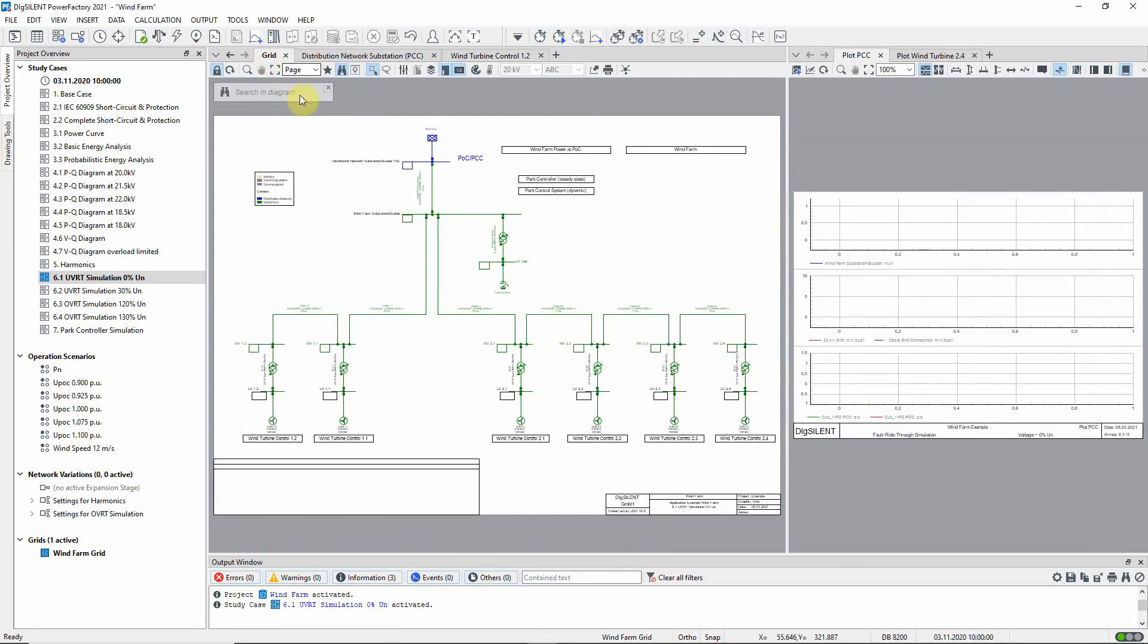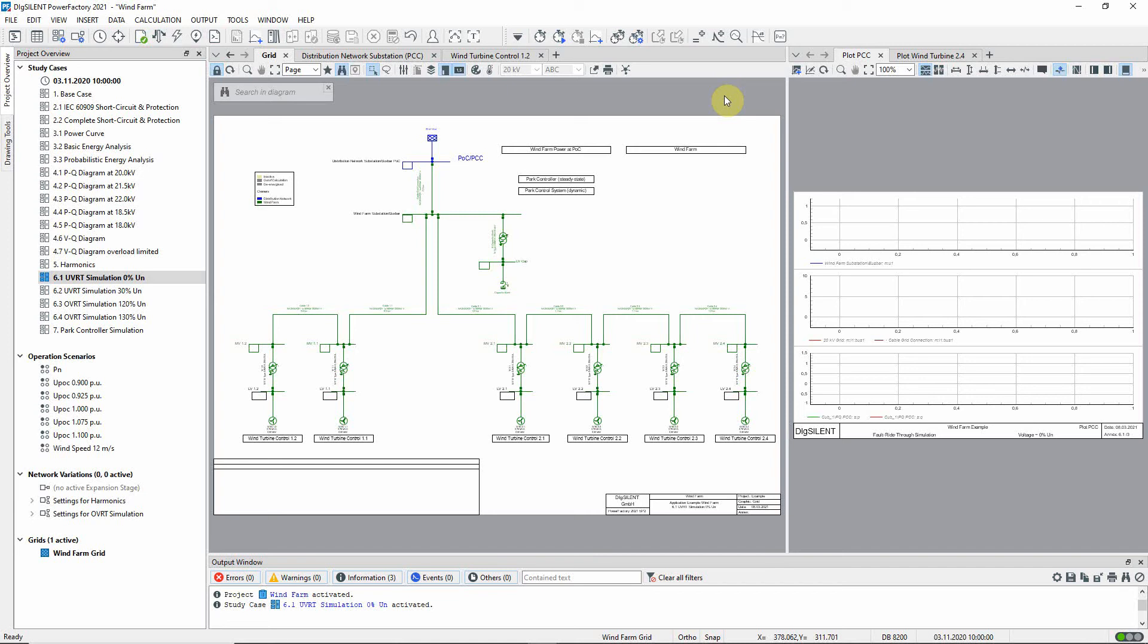In this example, we will apply a fault very close to the point of common coupling. This will cause the voltage at that point to fall to zero. The turbines in the wind farm are configured to inject additional reactive current into the network to support the voltage in the event of such a fault. We are going to carry out a dynamic simulation to demonstrate this behavior.